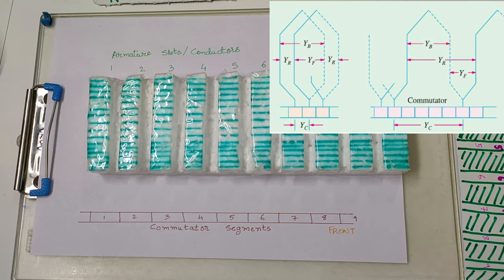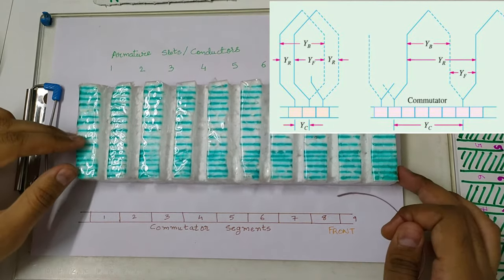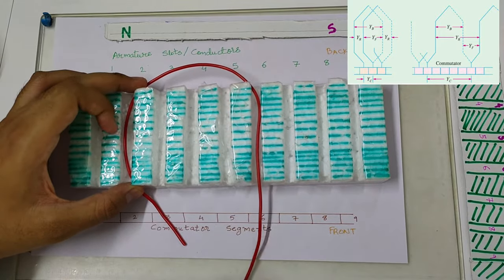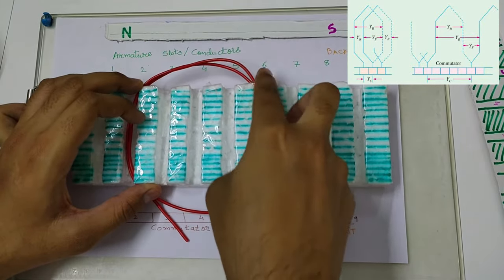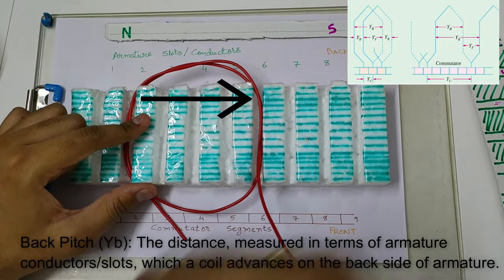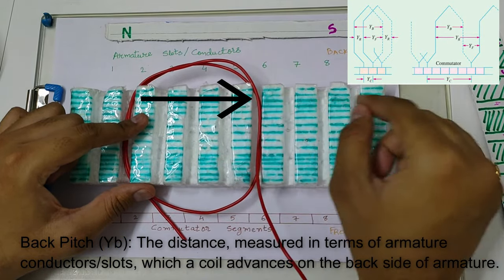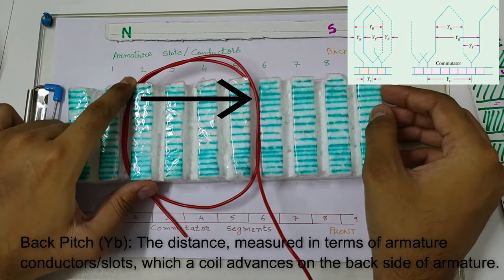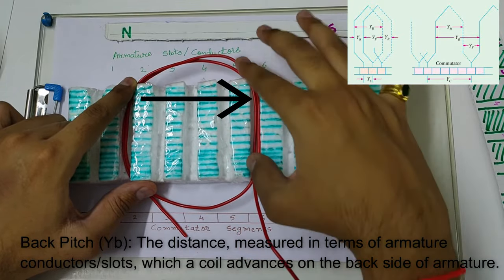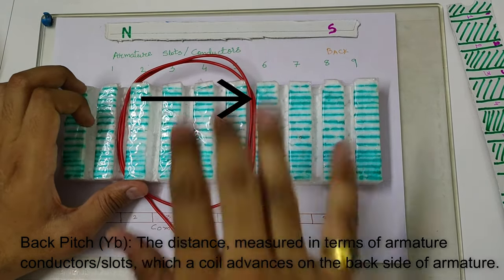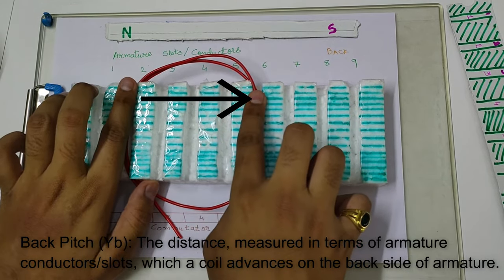Now let us learn the different pitches of the winding. You can see an image on your screen — this is the diagrammatic representation of the pitches. First, we will start with back pitch. Suppose we have a lap winding — then the lap winding would be going around like this. Back pitch is defined as the distance the coil advances on the back side of the armature, in terms of armature slots. Or we can call it the distance between the start of the coil and the end of the same coil on the back side. In this case, it is starting from this slot — 1, 2, 3, and 4. So 4 is the back pitch.